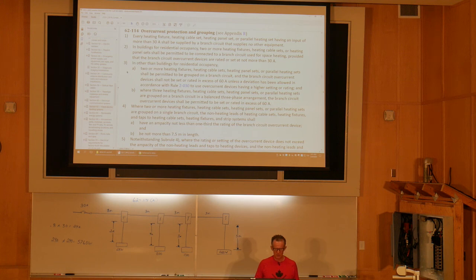In other than buildings for residential occupancy, 2 or more heating fixtures, heating cable sets, heating panel sets, or parallel heating sets shall be permitted to be grouped on a branch circuit, and the branch circuit overcurrent devices shall not be set or rated in excess of 60 amps unless a deviation has been allowed in accordance with Rule 2-030 to use overcurrent devices having a higher setting or rating. 2-030, that's your special permission by the authority having jurisdiction, so that's the inspection department.